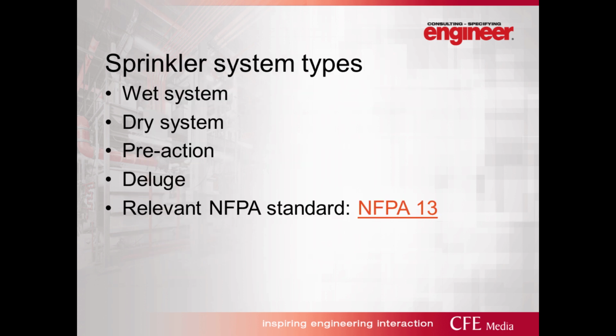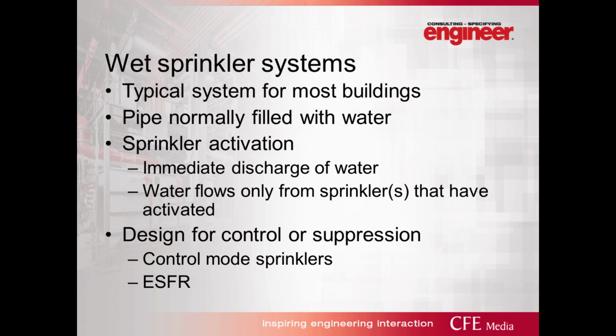Okay, let's talk about suppression types for a little bit. I would assume that most that are on this understand the sprinkler system types, so I'll roll through them pretty quickly, but there are typically four. They are all found in NFPA 13, which is the automatic sprinkler standard. The first system is a wet system. We'll talk about it in a moment. The dry system, what is called a pre-action sprinkler system, and finally a deluge system.